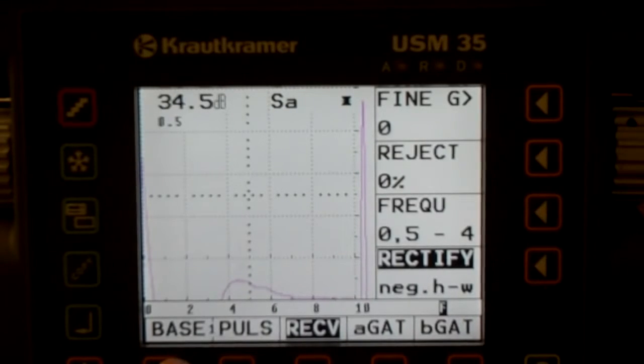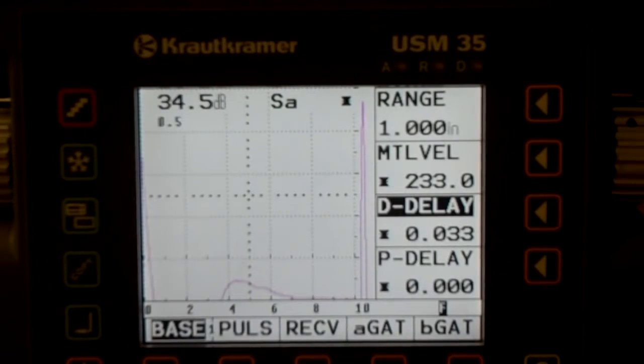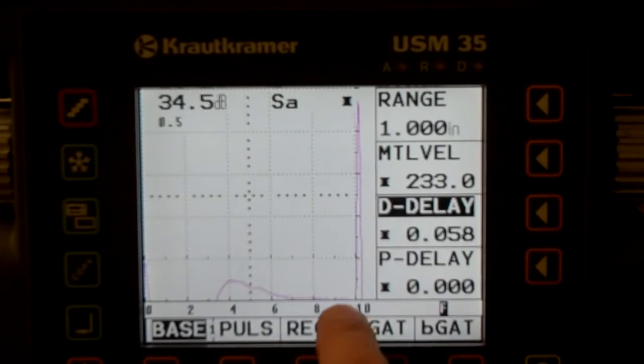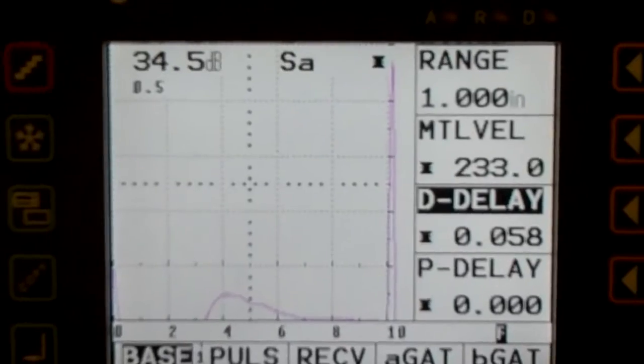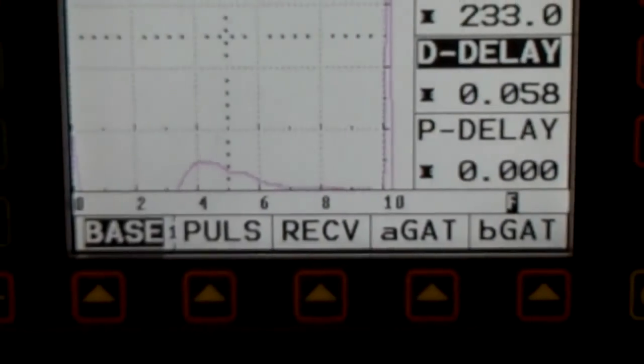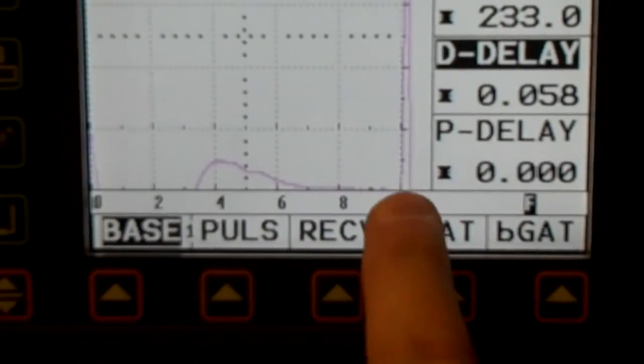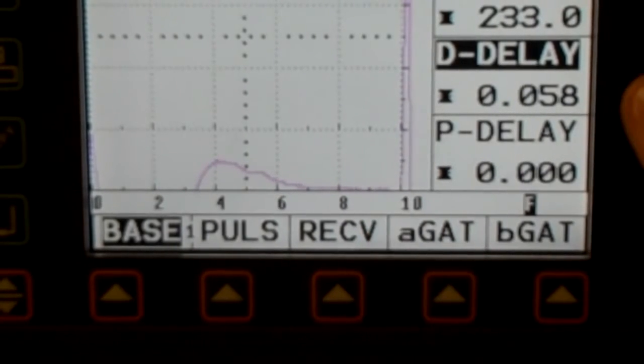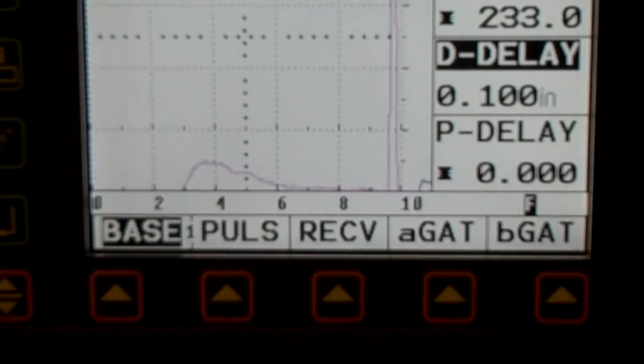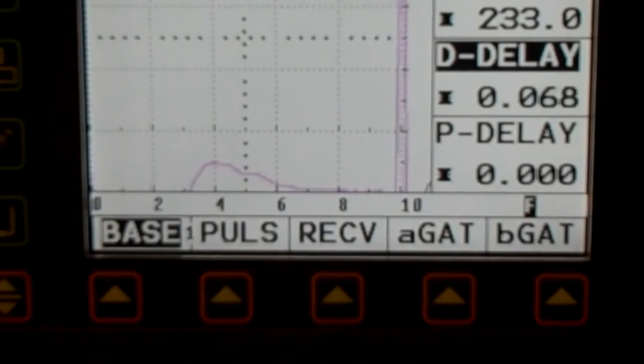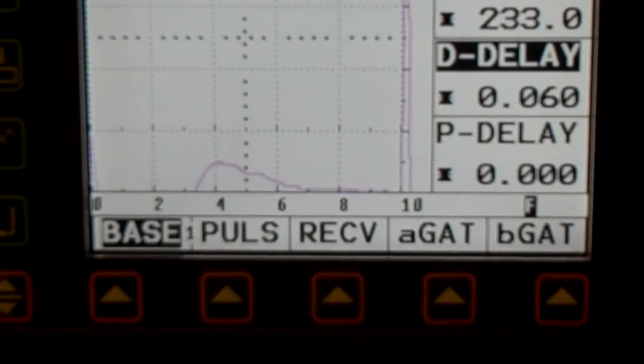So let's go to a base menu and push this over to where that's at 100% again, or 1 inch. That little 10 right there, we've got where the signal's breaking the baseline. Let me zoom you in a little bit. We're just looking right here where the signal breaks the baseline, and you can see that it's just a little bit in front of the 10. So we're going to take our delay, oops, we're jumping big here, we don't want to jump so big, and move it back. Now we're right on that 100%, which is good.